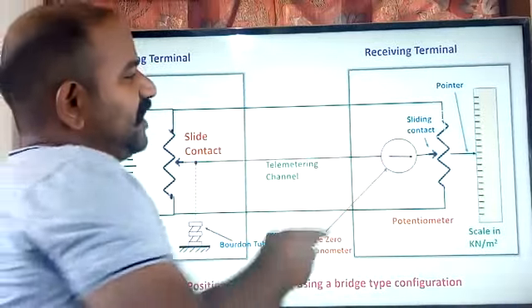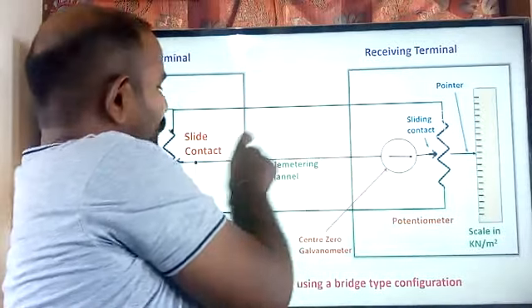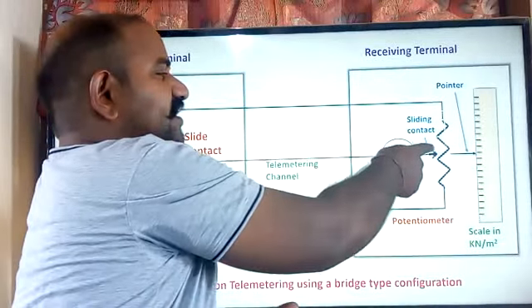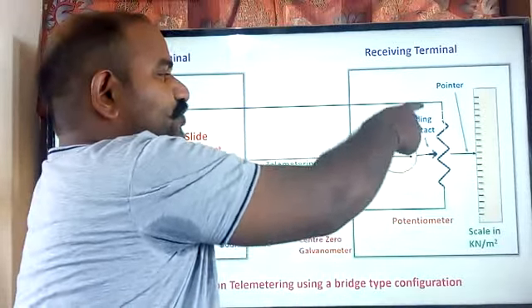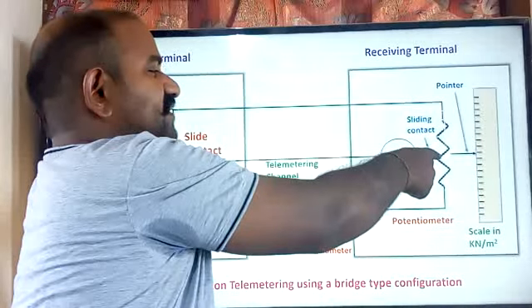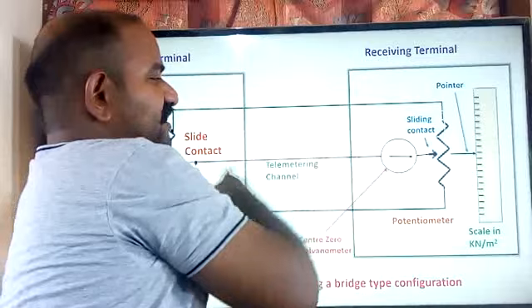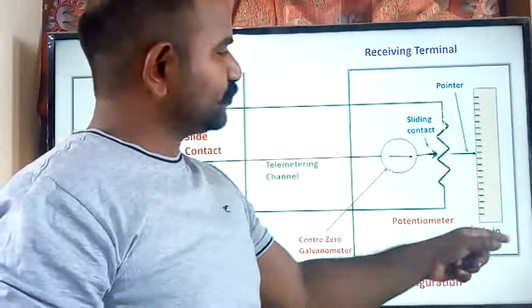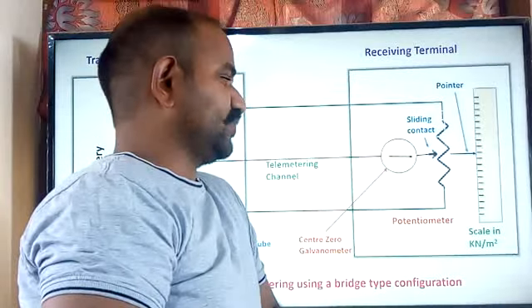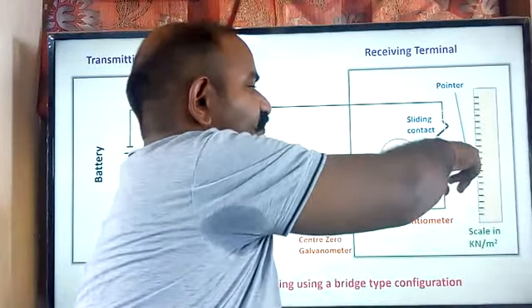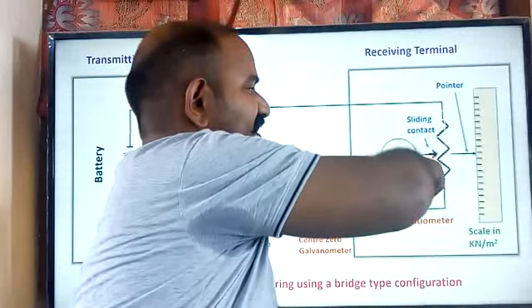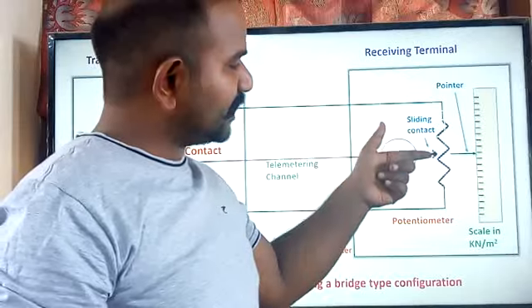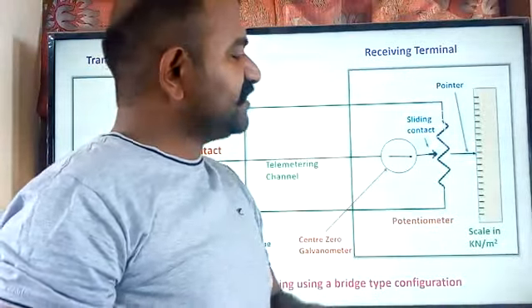At the destination, we use another sliding contact potentiometer such that, depending on the information coming through the telemetering system, the sliding contact adjusts its position to match the position of the transmitting end. One end of this sliding contact is connected to a scale which shows the information in terms of pressure in kilo Newton per meter square. Whenever there is a change in the sliding contact position, the same change is reflected on the scale to indicate how much pressure is being sensed from the Bourdon tube.